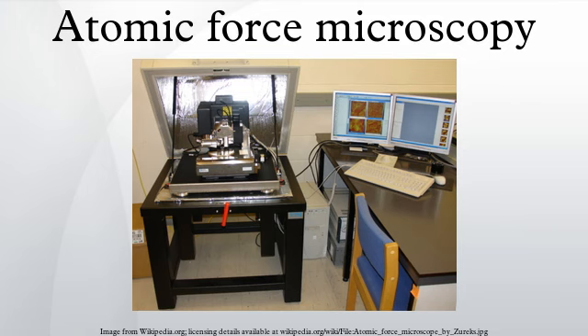Piezoelectric scanners. AFM scanners are made from piezoelectric material, which expands and contracts proportionally to an applied voltage. Whether they elongate or contract depends upon the polarity of the voltage applied. The scanner is constructed by combining independently operated piezoelectrodes for X, Y, and Z into a single tube, forming a scanner that can manipulate samples and probes with extreme precision in 3 dimensions. Independent stacks of piezos can be used instead of a tube, resulting in decoupled X, Y, and Z movement.